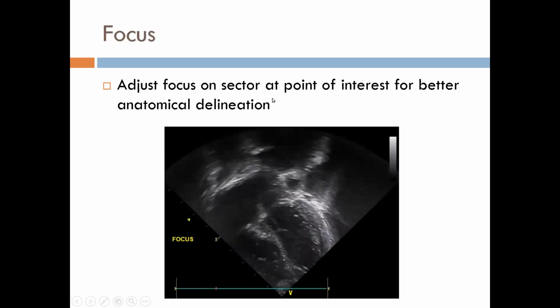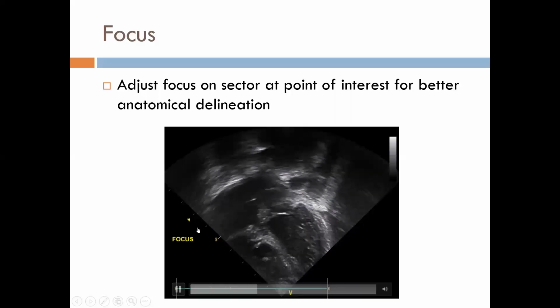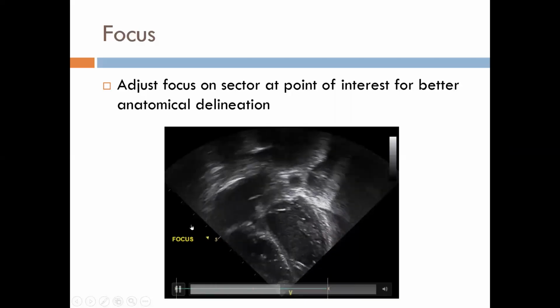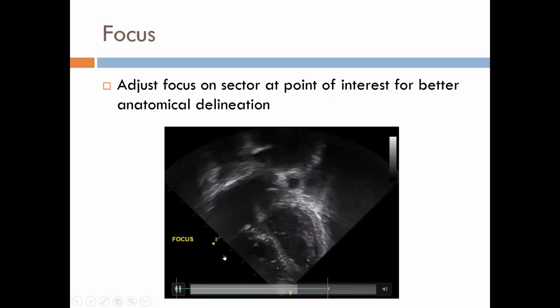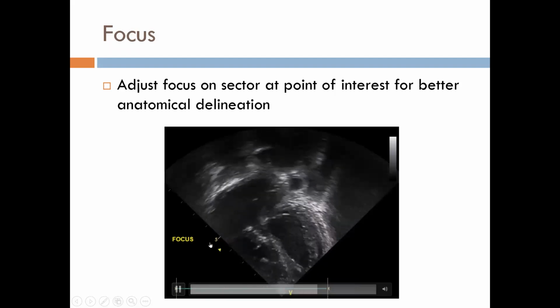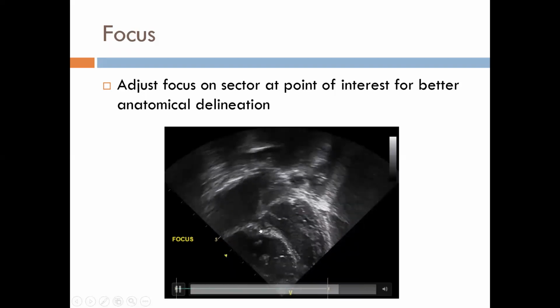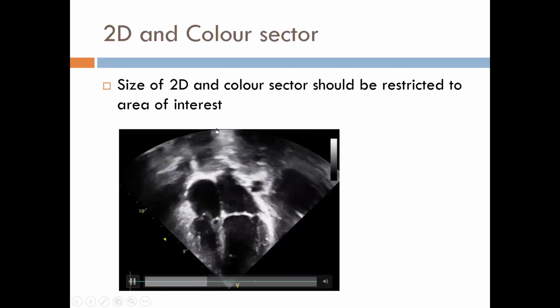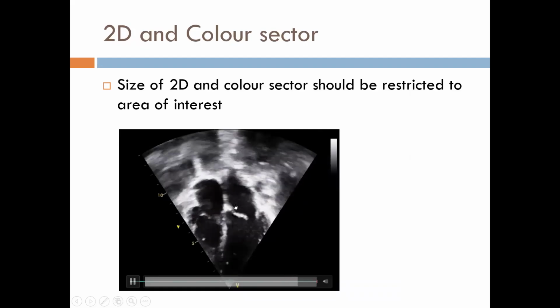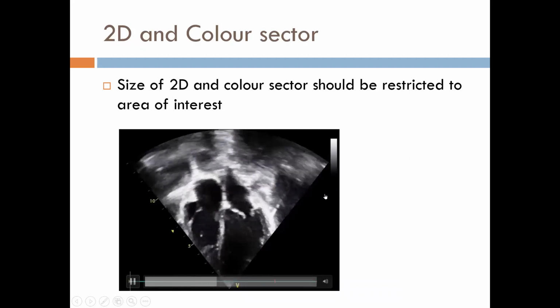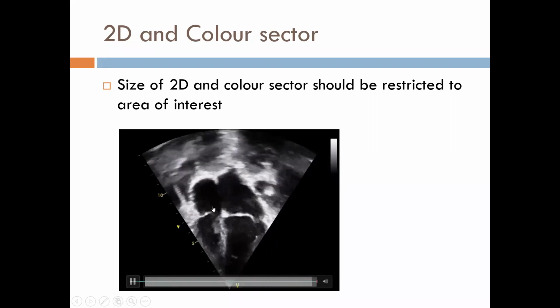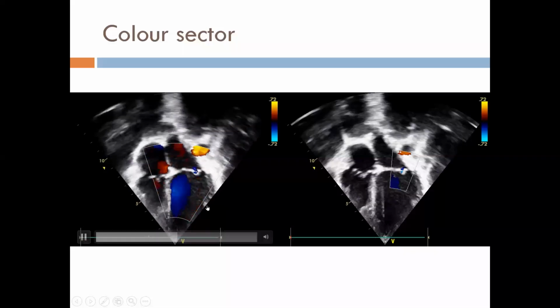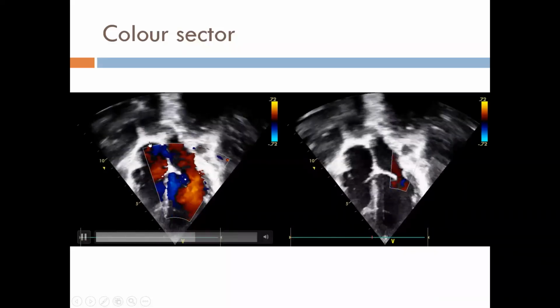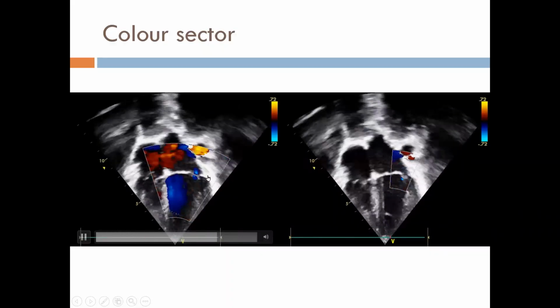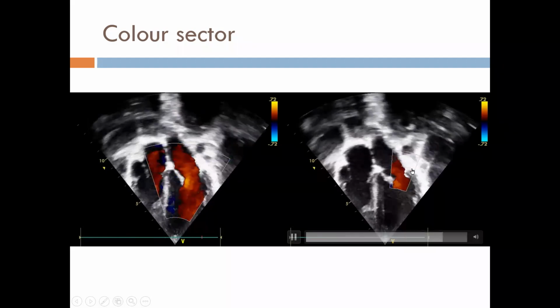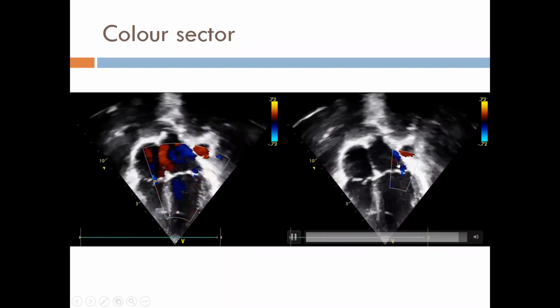Adjust the focus of the sector at the point of interest for better imaging. If you are interested in a VSD, this particular point has to be adjusted with the help of the knob given on the keyboard. Whatever place you keep the focus, that particular area will be highlighted better. Size of the 2D and the sector: if the heart is small, why keep such a big sector? You can narrow the sector size so that you get a clearer image. Similarly, it is true for the color also. Why do you want such a big color sector if you want to see only the mitral valve? So reduce the color sector to a smaller size.